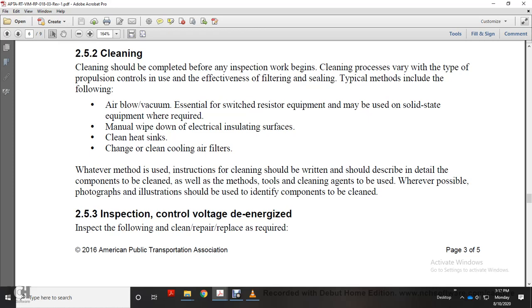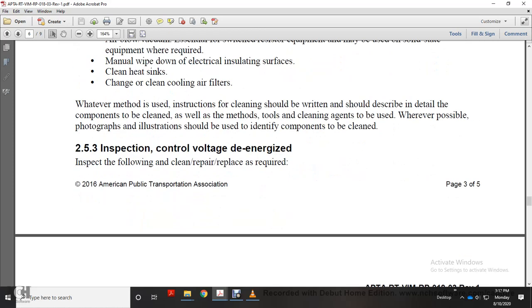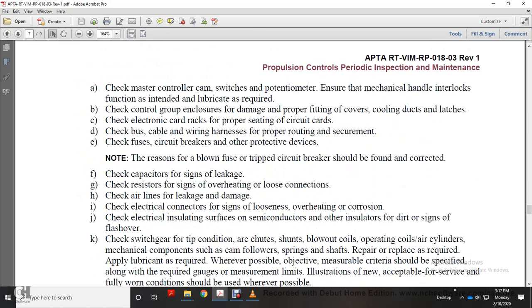2.5.3, inspection with control voltage de-energized. Inspect the following, and clean, repair, and replace as required. A. Check the master control cam and the switch for the potentiometer, ensure the mechanical handle interlock functions, and check whether lubricant is required. B. Check the control group enclosure for damage, and proper fitting of the cover, cooling ducts, and latches. C. Check the electronic card rack for proper seating of the circuit cards. D. Check bus cable and wiring harness for proper routing and securement. E. Check fuses, circuit breakers, and other protective devices. Note: the reason for a blown fuse or tripped circuit breaker should be found and corrected.